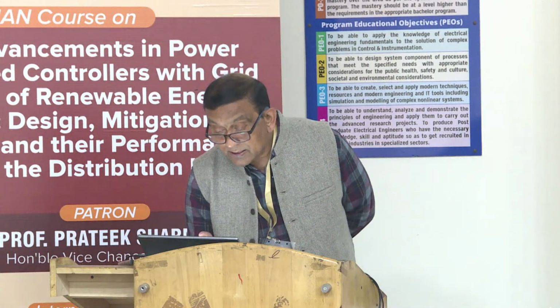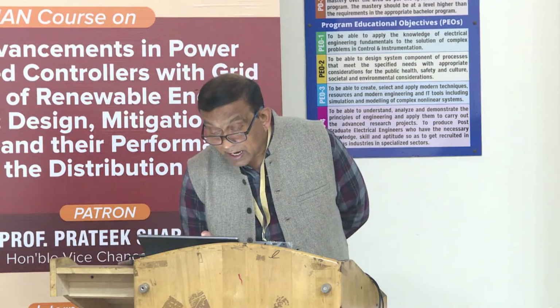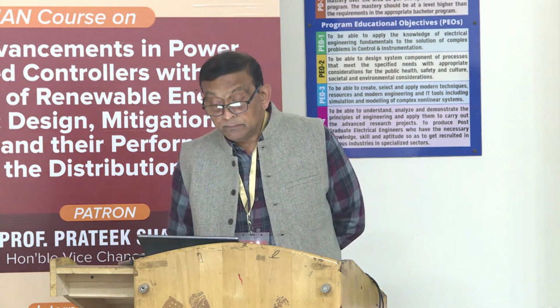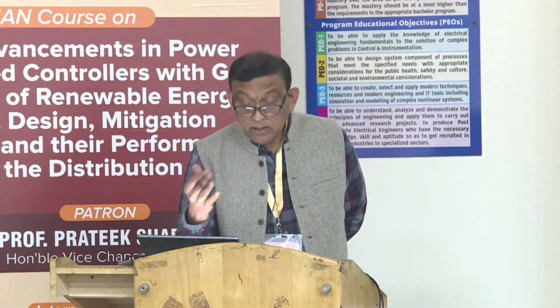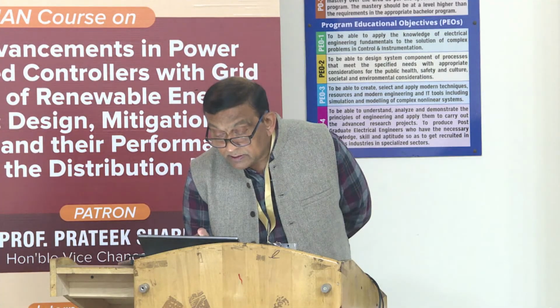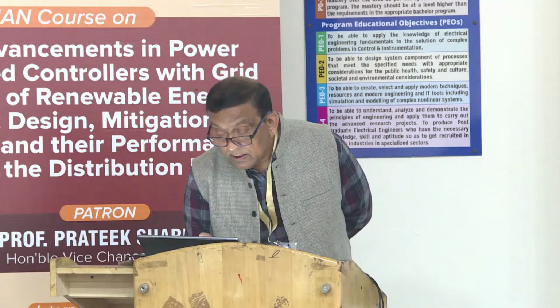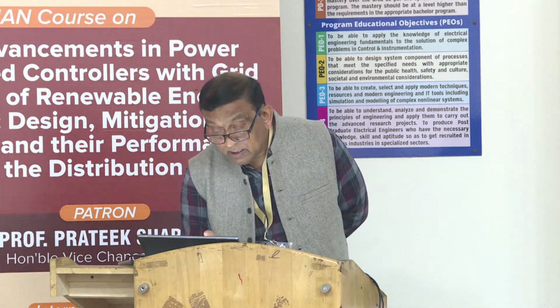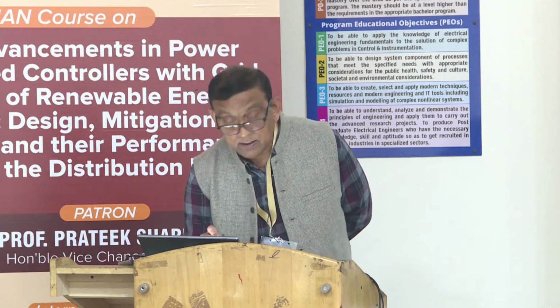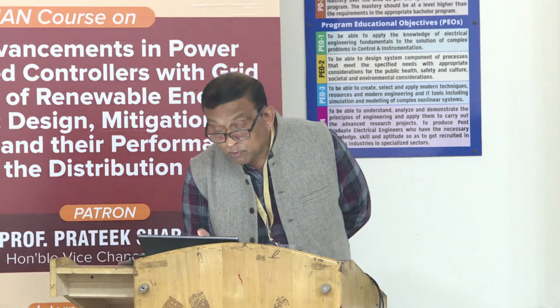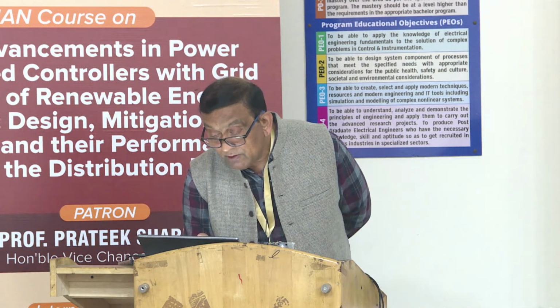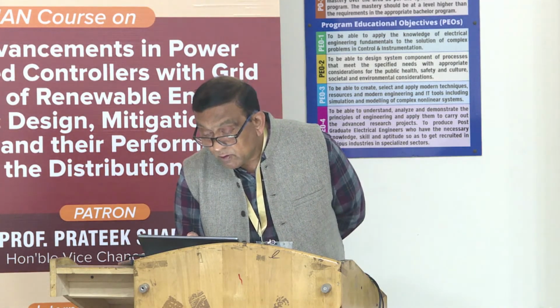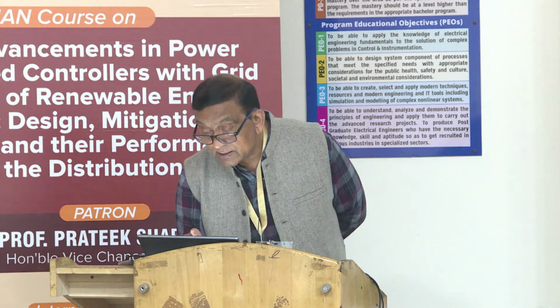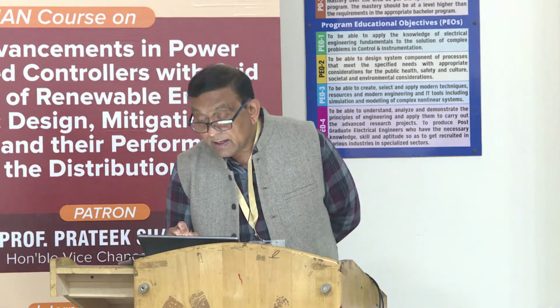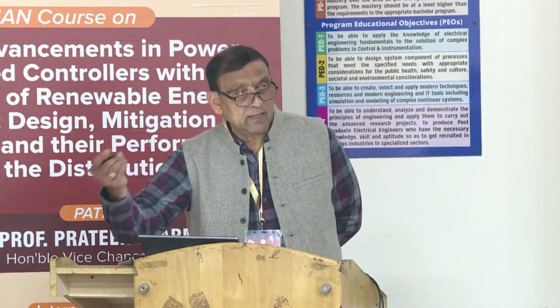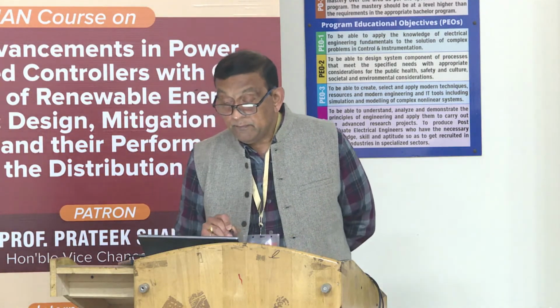As far as higher harmonics are concerned, if harmonics are between 11th and 17th harmonic, like 11th, 13th or 15th, the limit is reduced. So if harmonic ranking is increasing, the limit is also more severe. For higher frequency harmonics, limit is more severe. You see here it's 2, then from 17th to 23 it is 1.5, from 23 to 35 it is 0.6, and harmonics ranking more than 35, up to the 50th harmonic, this is 0.3%.